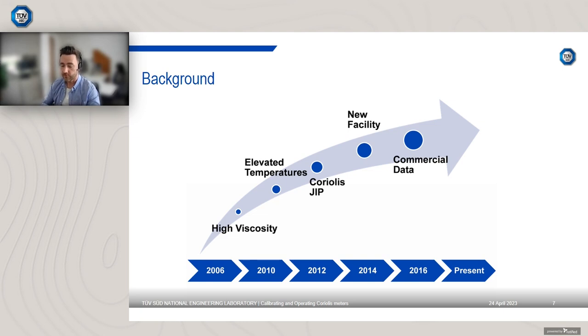However, there was a lack of traceable flow facilities in the world that could operate at elevated temperatures and pressures. So the kind of temperatures and pressures you might operate in the oil and gas industry, for example. Most calibration facilities across the world operate at 20 to 30 degrees Celsius, and relatively low pressure for oil calibrations, certainly below around 5 bar. So we found that there was a need for a new facility. So we came up with an idea for this new facility, helped design it, helped build it, constructed it, and it was built between the period of 2014 and 2016.